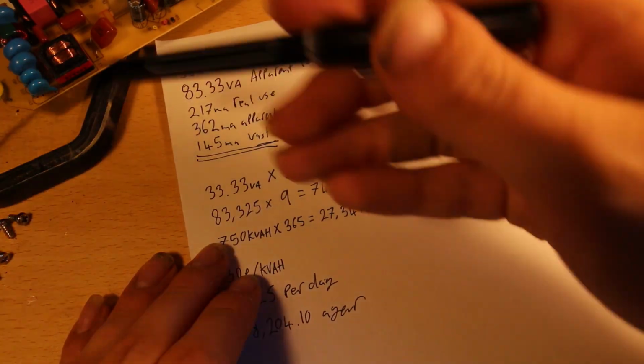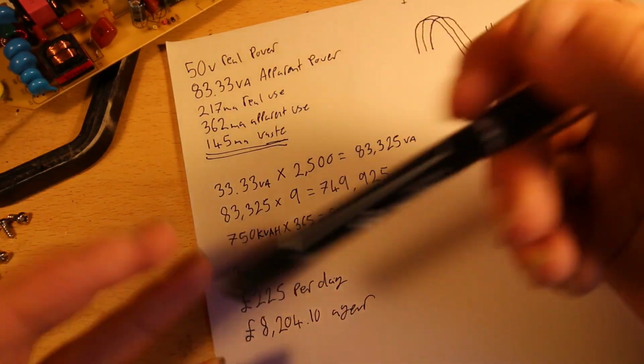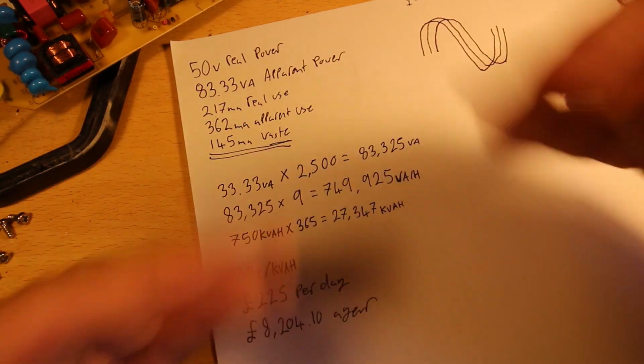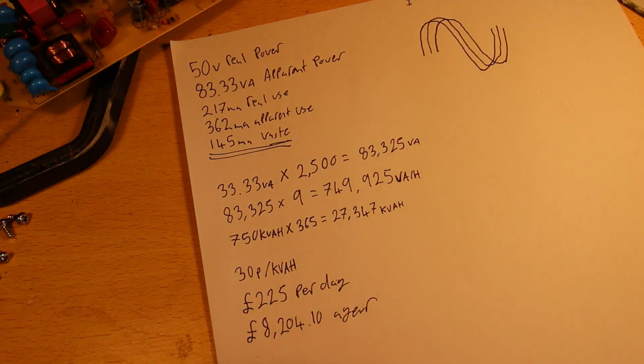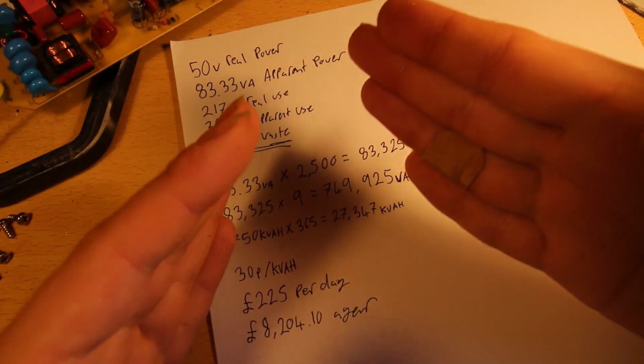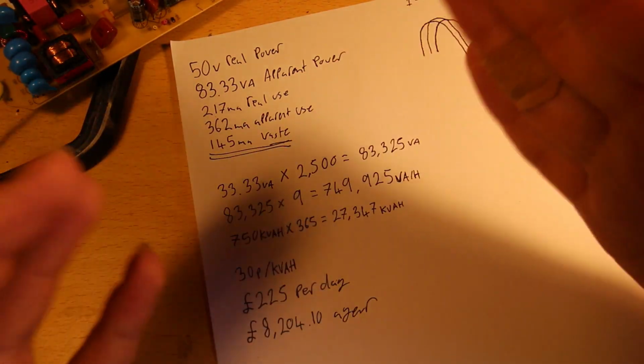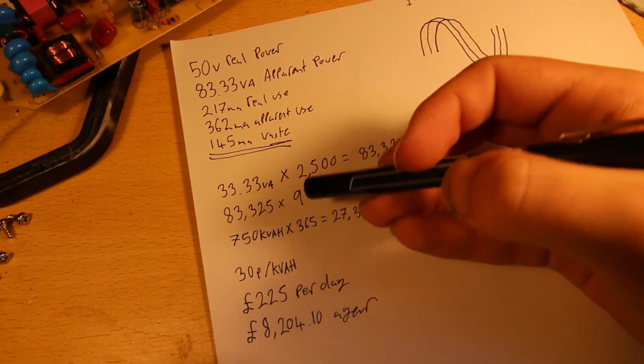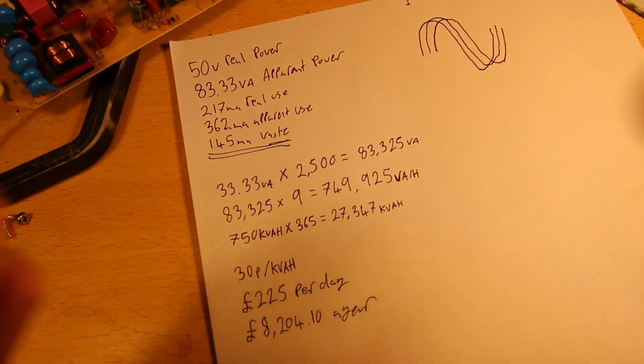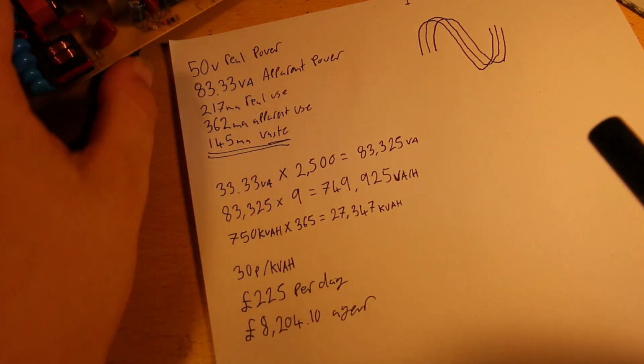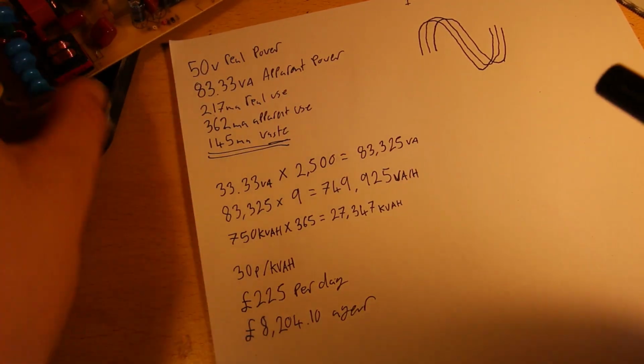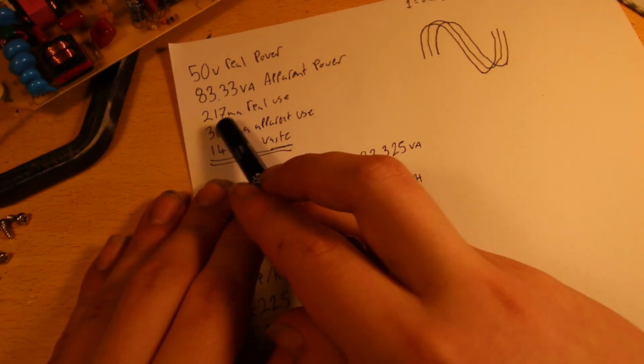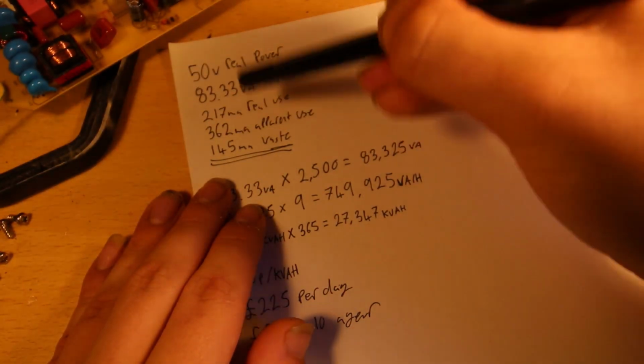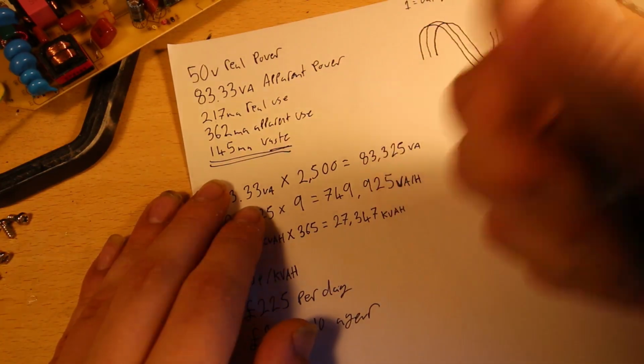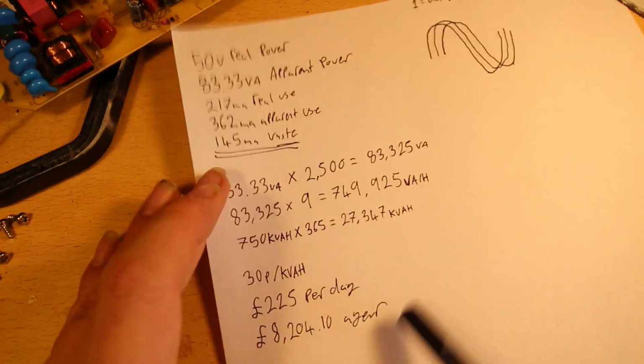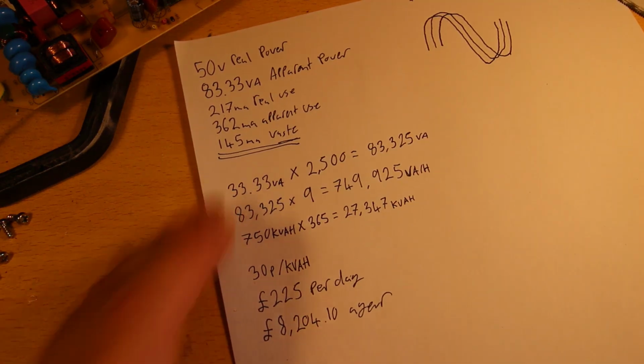Because this 33.3 volt amp per fixture is not being used. It is just being temporarily stored and then returned to the grid, but you're still billed for it because the transformer still has to be big enough to supply it, the cable still has to carry it, there's still losses involved in that. So this can very quickly escalate to get very, very expensive, which is why you get power factor corrected fittings like this. So this one would only actually draw the 217 milliamps, not the 145 extra that we don't need. That saves us this money, £225 a day.